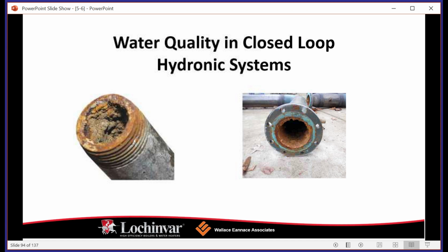So again, as a service technician coming in, you're going to ask your end user, have you had any issues? Were there noises? Were there any spots where the building wasn't heating properly? We're going to go through, we're going to inspect the interior of the cabinet. Again, clean and vacuum if necessary. You shouldn't really see too much accumulated stuff inside the boiler cabinets if the boiler space is clean and we're pulling fresh air from a good area where we don't get outdoor contaminants.